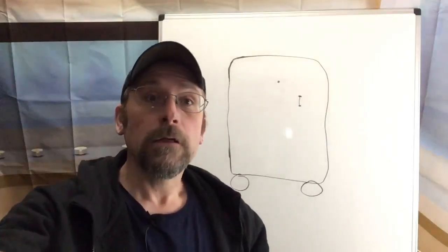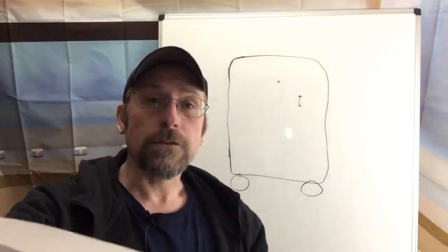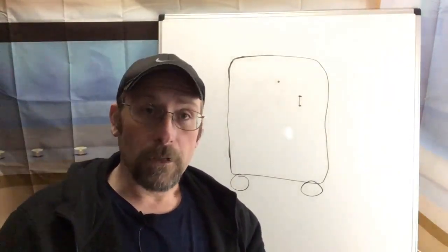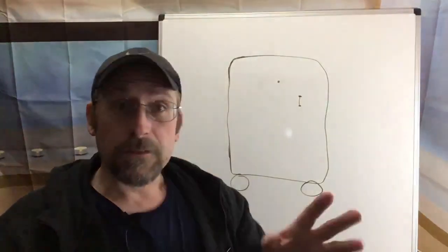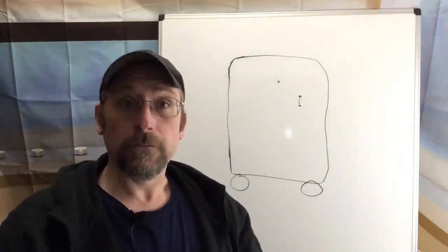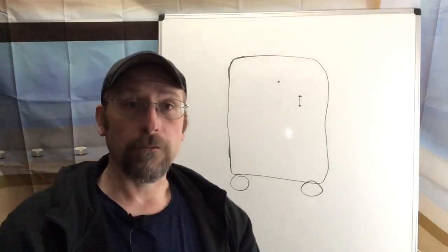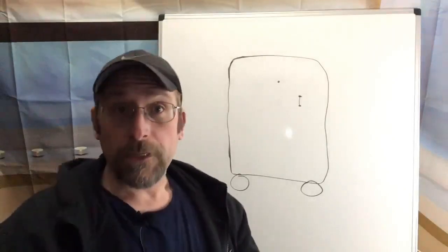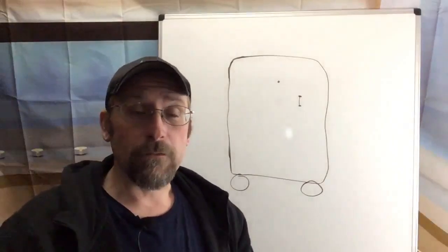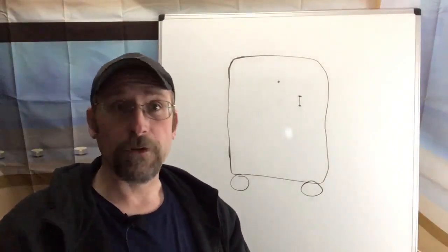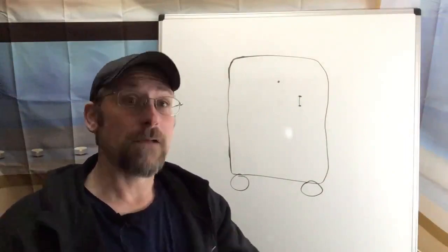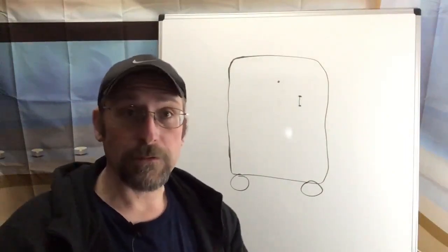Today we're talking about how to make an oxygen concentrator quiet. I get this question a lot because the unfortunate reality is a lot of these machines are loud. They're loud for a variety of reasons - one being that they're an oxygen machine and you're pretty much guaranteed to have a machine putting out a minimum of 30 decibels upwards of 60, 70 decibels, sometimes even louder depending on the problems with the machine.